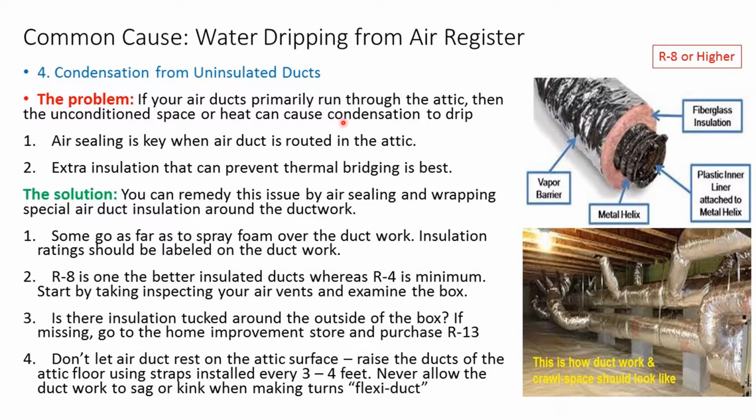Sometimes air ducts in the attic, if they're sagging, if the insulation's not too good, it's the old style like an R4, or the insulation's missing, the heat in the attic will definitely affect it. For those flex ducts, which these are, I recommend an R8 or higher. Flex ducts tend to want to fall, so every 3 to 4 feet you want to put a strap on it, make sure it doesn't sag, because if it does sag, it's going to have condensation as well.